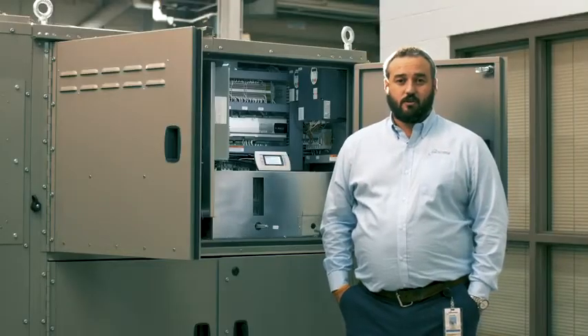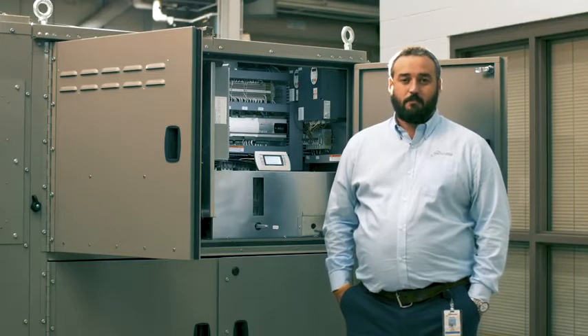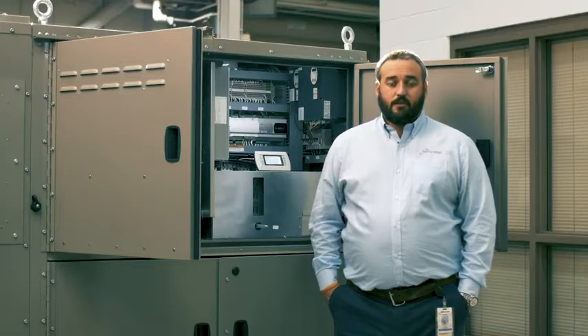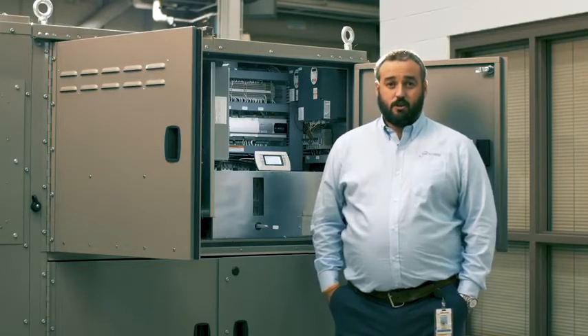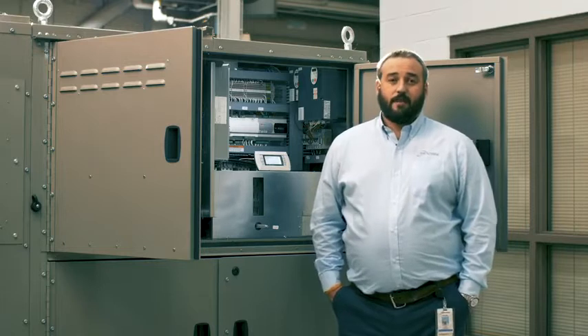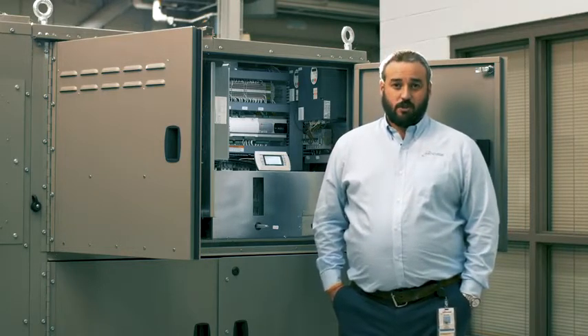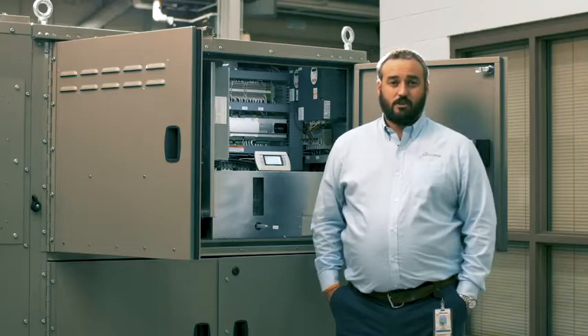Using the Carel controls, we offer BACnet over MSTP, BACnet over Ethernet, and LAN connectivity. And obviously that can connect into most large BMS systems. Using the BACnet card, we offer over 200 variables that the customer can monitor. 45 of those points are read-write variables, which means the customer can actually interface and make changes to the unit. Some of them are damper control and fan control, and this gives him the opportunity to do enthalpy economizer using his own BMS, or duct pressurization, or even building pressurization.